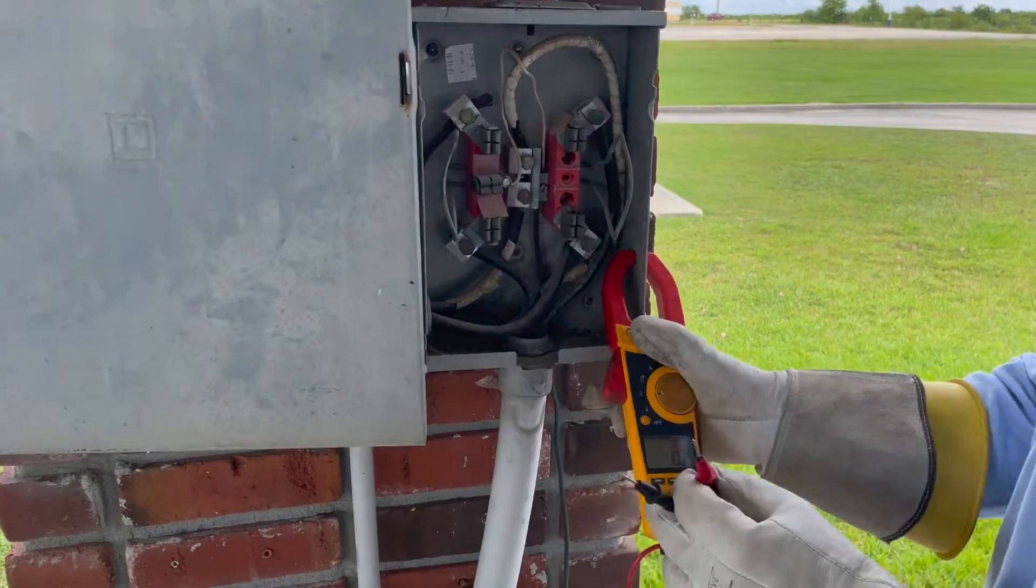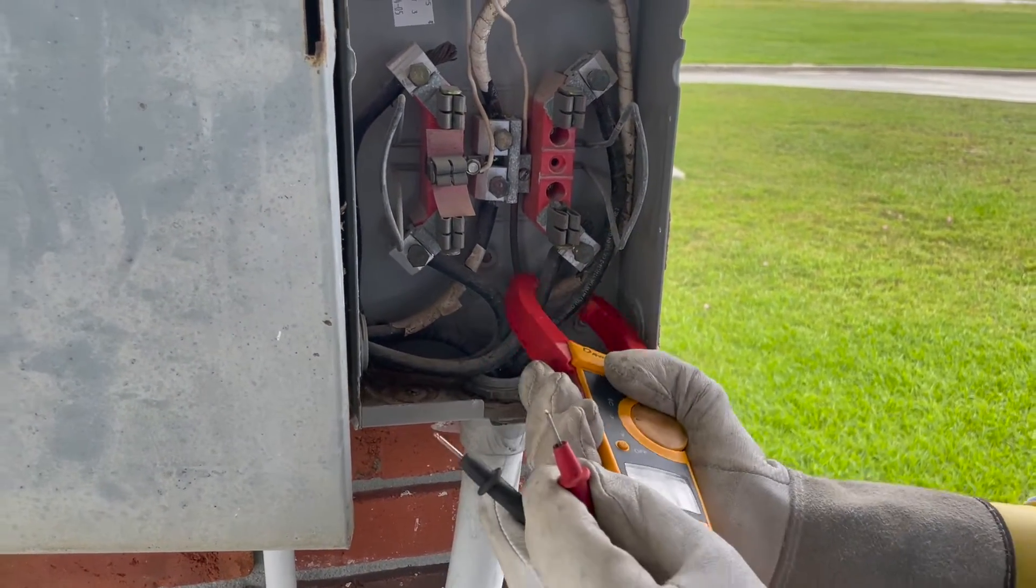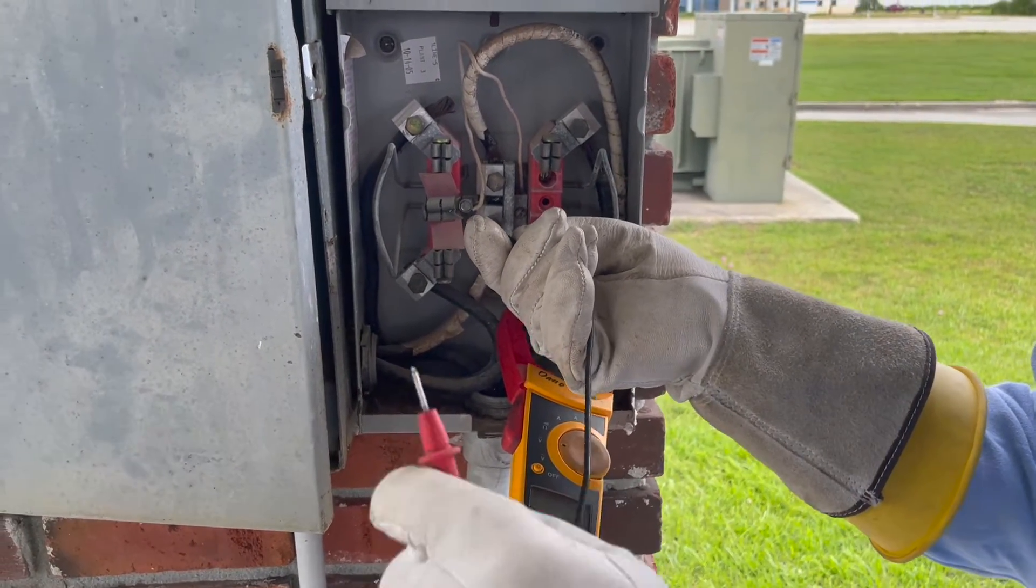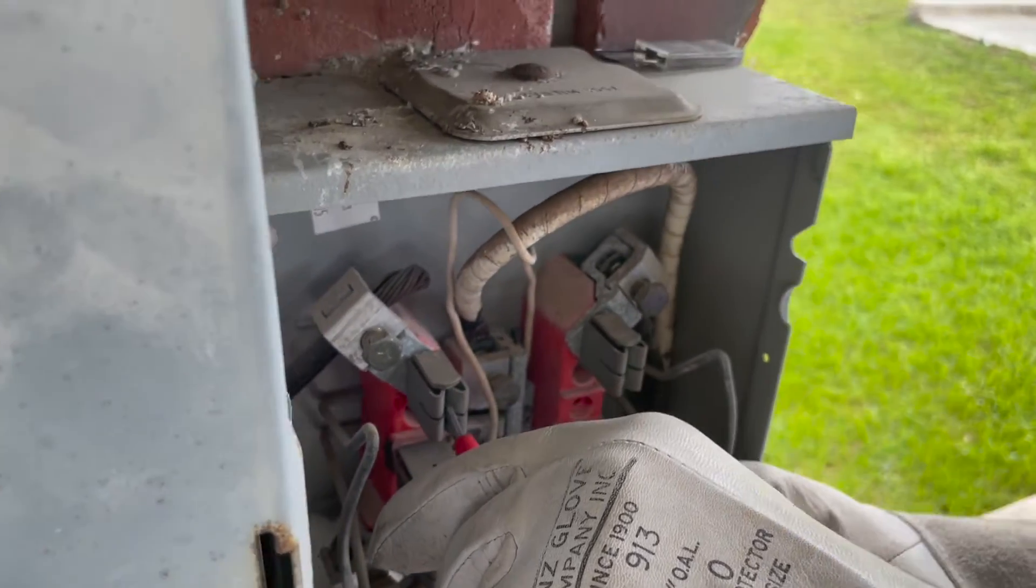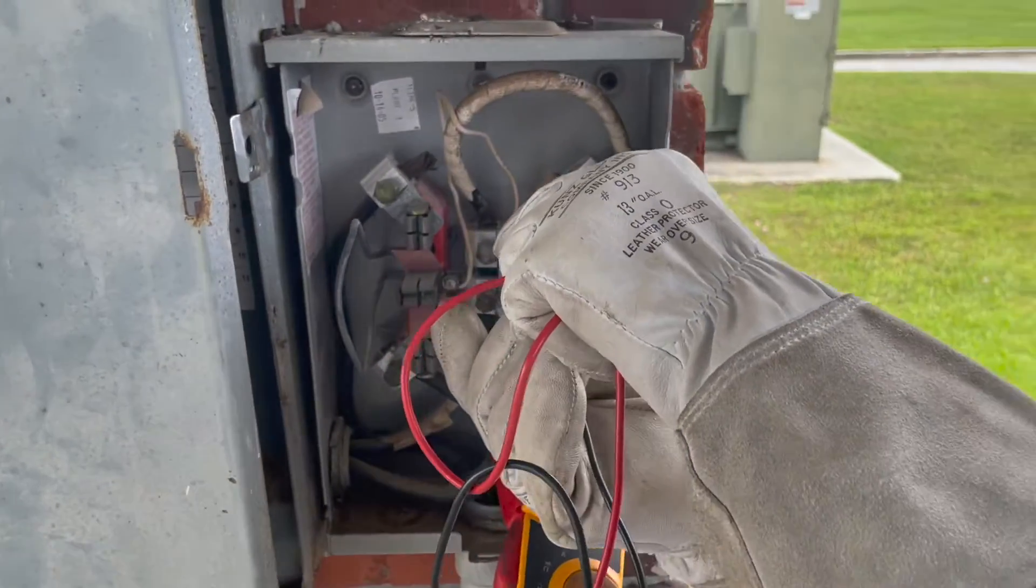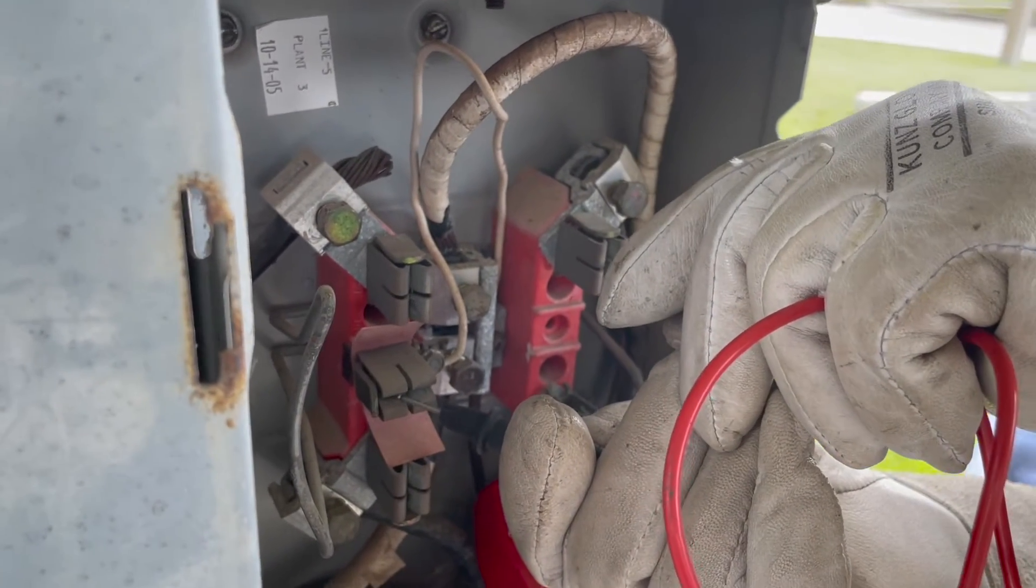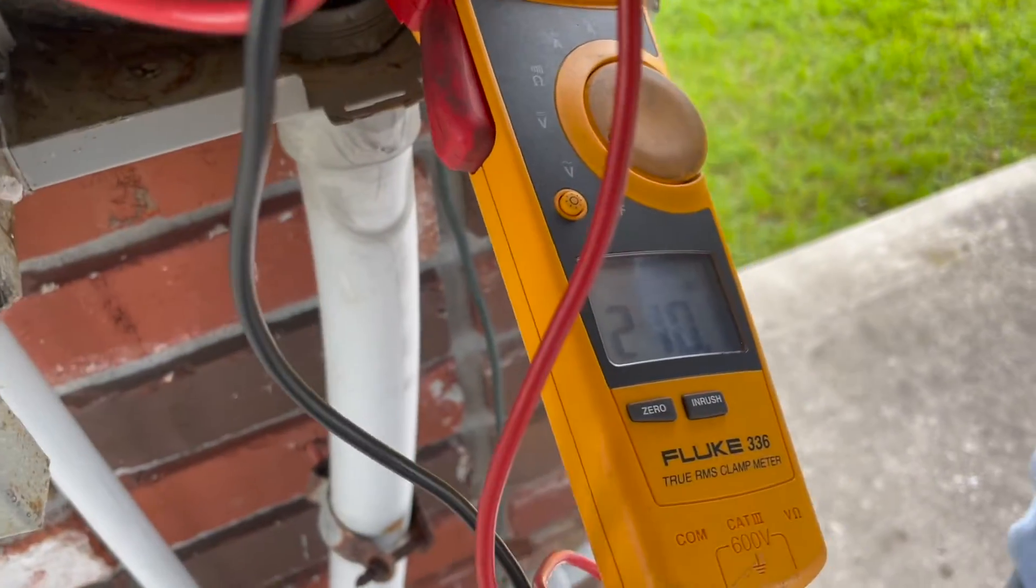The service would come up and you would check the voltages. These are going to be your voltages. This is your ground, so you're going to go phase to ground: 120 volts phase to ground, 123 volts. Phase to phase we have 210 volts. This is a 120/208 service.